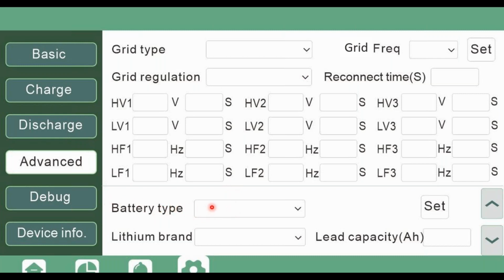And so here we select battery type. You can run your inverter with no battery, right? You can use it with no battery, just grid and PV production, or just PV production as well. So here you would select battery in order to commission with closed loop communication with our batteries, right? Battery lithium: select lithium, and then on lithium brand, we would select lithium zero, okay? We don't need to stipulate any capacity because that is a reading that will come straight from the BMS. So lead capacity would be if you're using a lead acid battery type.